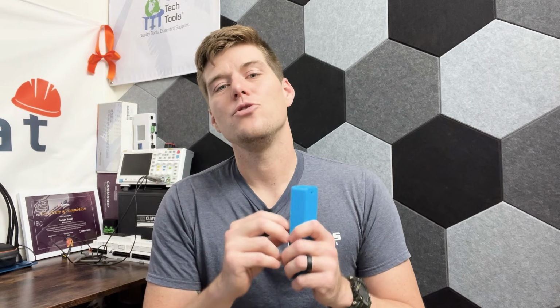So the two words of caution here. Always drive to 0 before you plug it back into the board, or overdrive it past 0 to ensure that it is closed, because you can overdrive it closed. And then the second thing is, do not drive them way beyond their limits open, because you may cause damage to certain expansion valves, or they may become decoupled inside of that expansion valve itself on direct drive, not indirect drive. So see you guys on the next one.